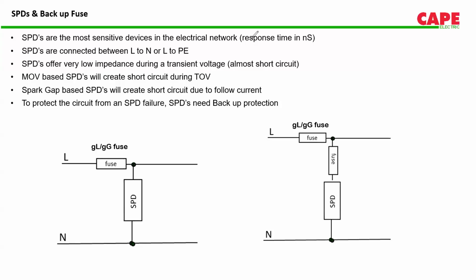See, suppose this is a connection. In this connection, you see the SPD is connected between line and neutral. And we have a fuse. Let us call this fuse F1. It is the main incomer fuse. Right. So in this case, suppose an SPD fails.